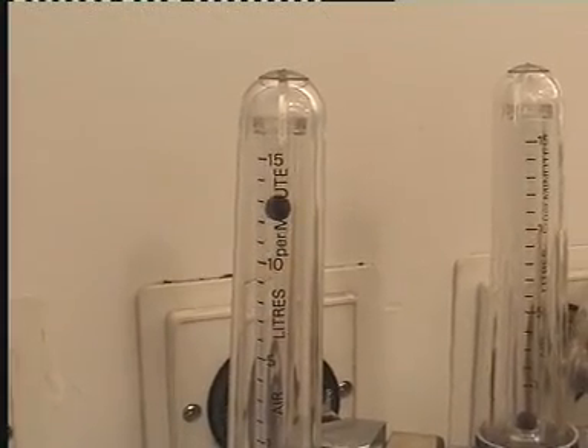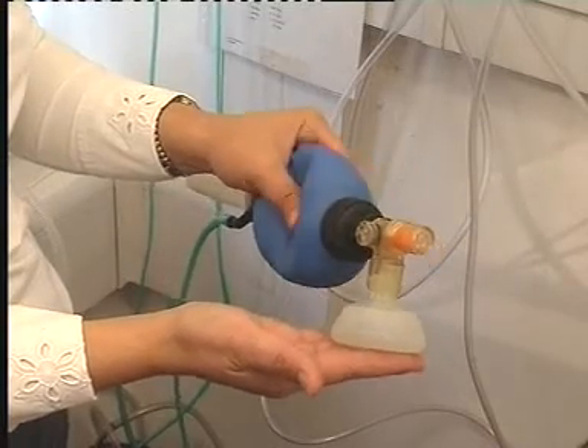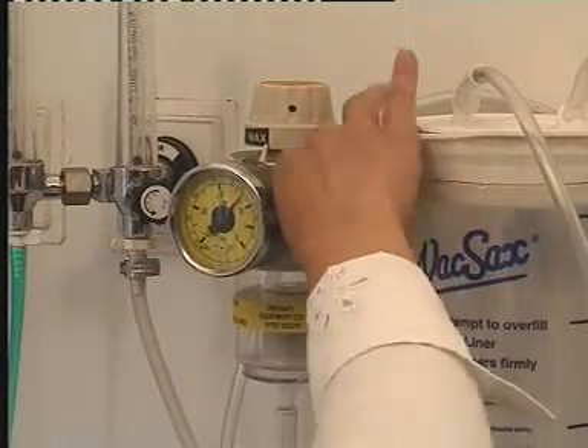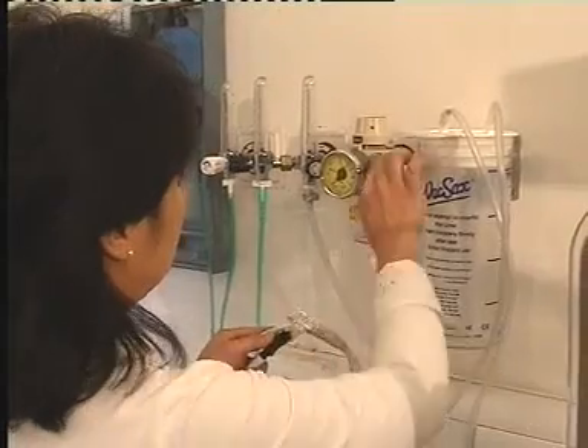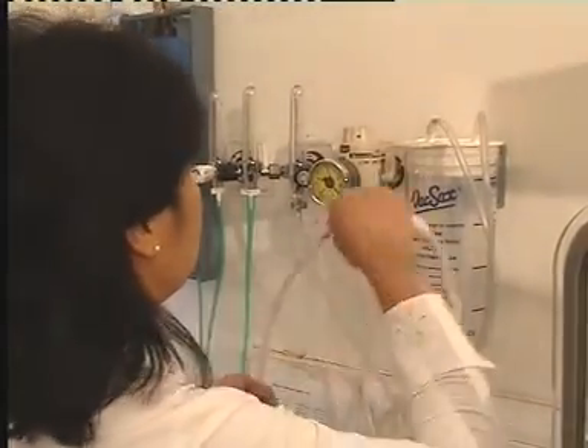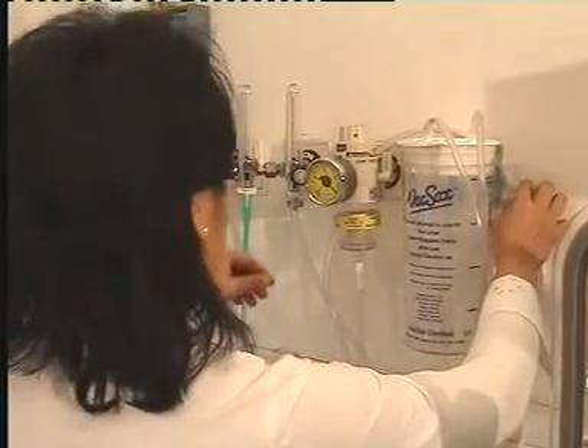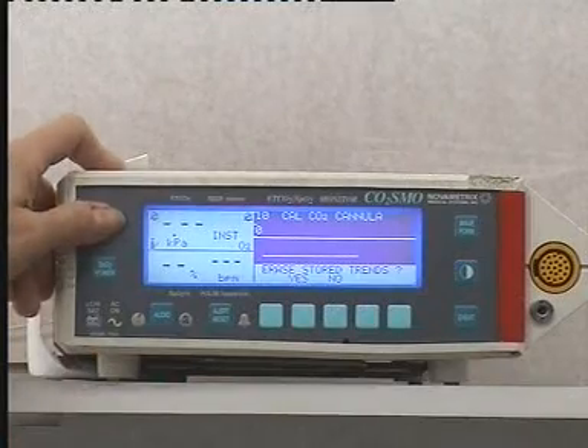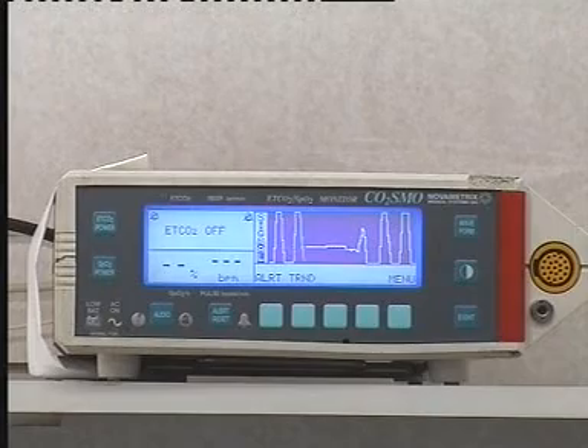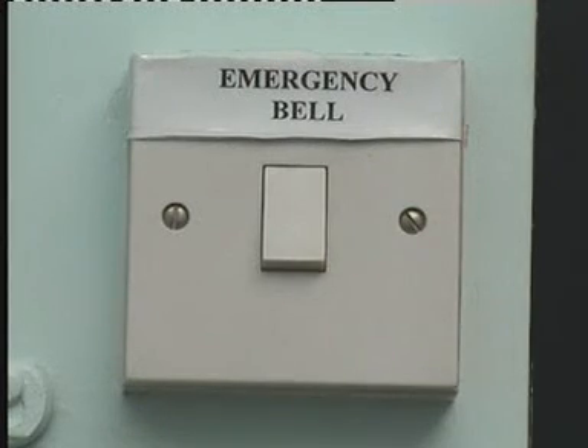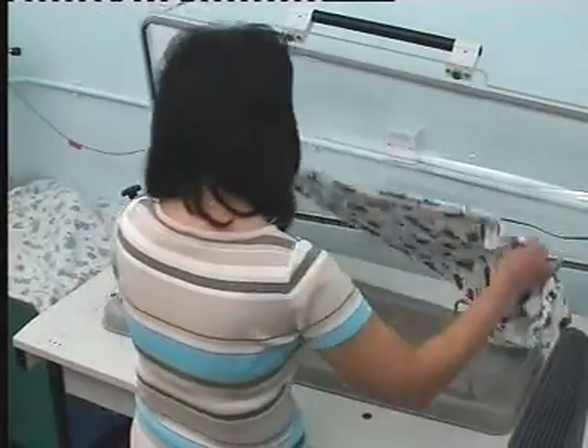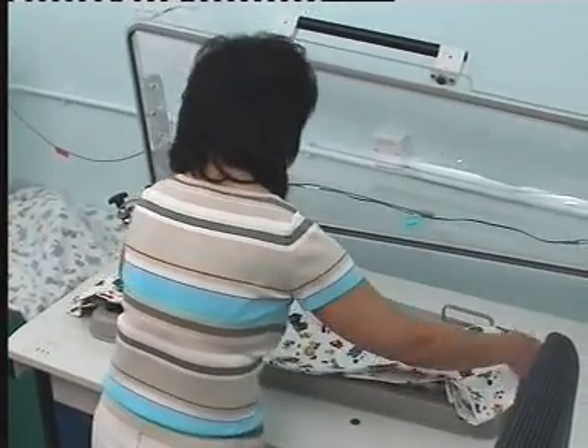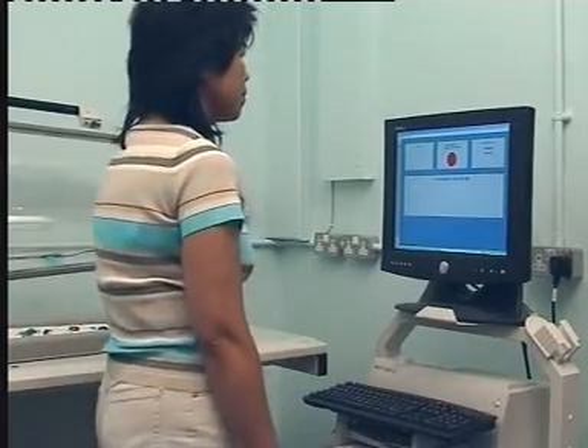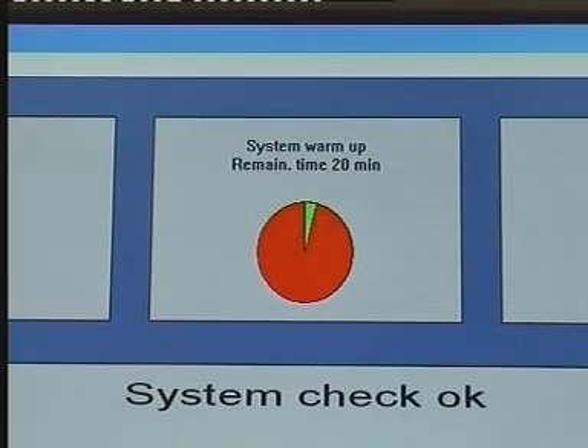On the day of the lung function tests, it's important that 2 skilled, trained staff are present, and that the resuscitation equipment is checked. Minimum requirements include oxygen supply, an ambu bag, suction apparatus, pulse oximetry, and an alarm system for contacting other members of staff. All equipment should be assembled, calibrated and checked prior to the infant's arrival. The pneumotach must be switched on to heat at least 30 minutes prior to calibration.